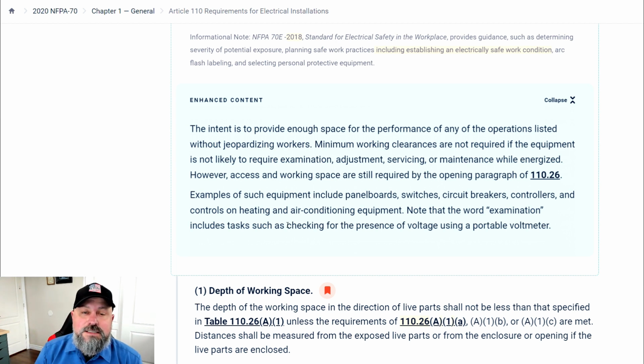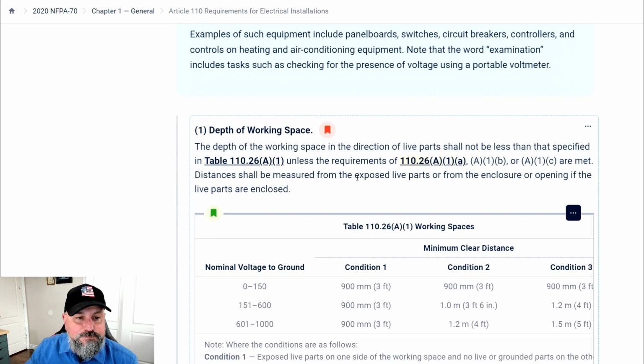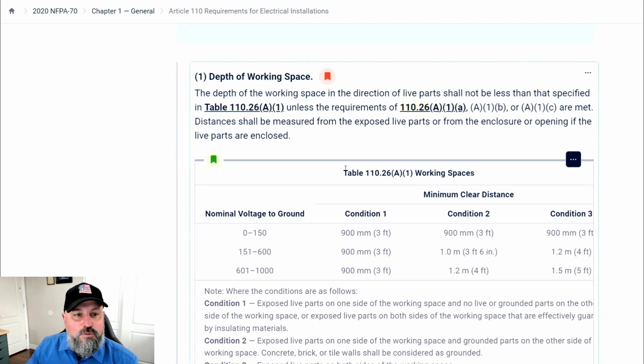So even if it doesn't have to be fully worked on while it's live, it still needs to be accessible for you to use your voltmeter and check the voltage on that equipment. So a lot of equipment does fall into this category. And so what we're going to dive into are what the conditions are to what the footage you need space-wise. So let's go here. Depth of working space, number one.